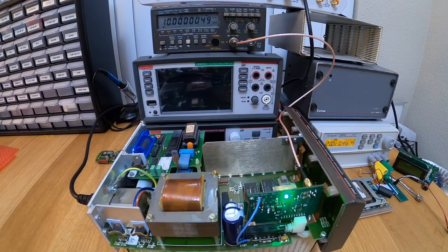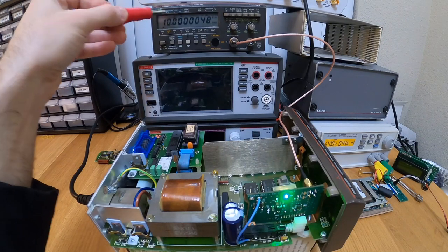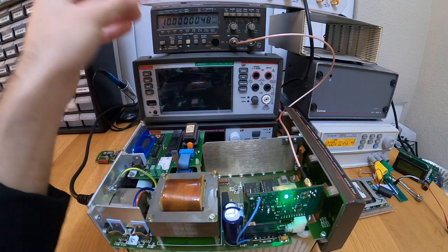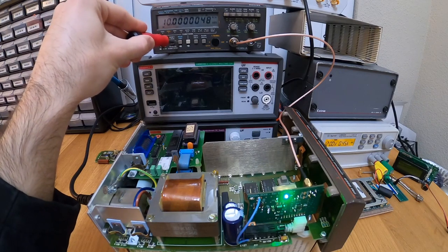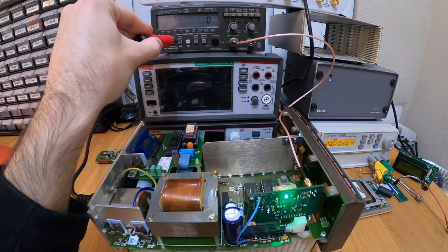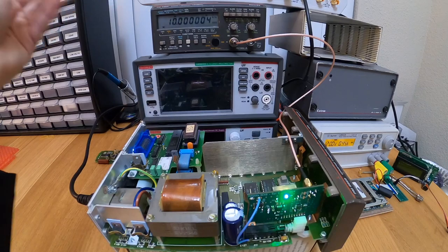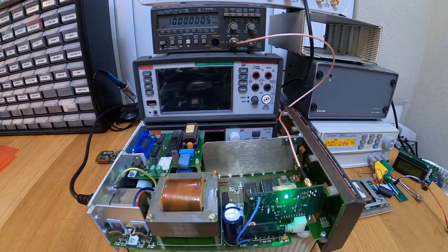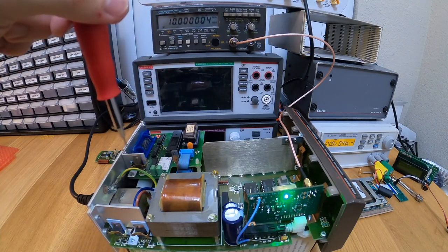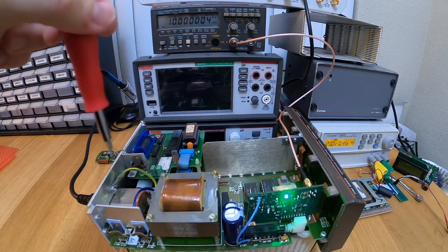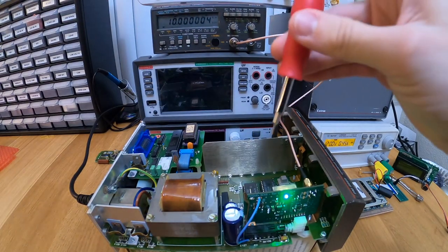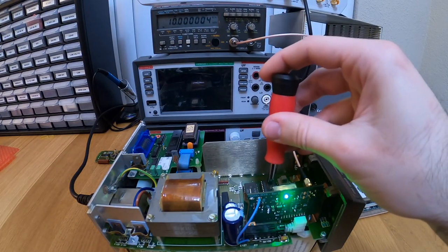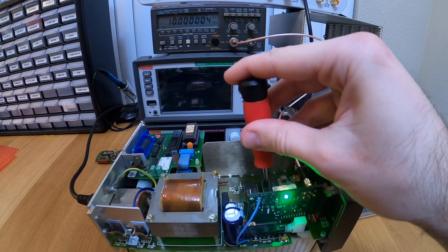So the first thing I want to do is do a coarse calibration. Currently, the reading frequency of the display here is 10 seconds, which is going to be a bit slow and inconvenient. So I'm simply going to change the measurement time to get a reading every second. I have less resolution, but for the initial calibration, it's going to be good. Just a word of caution: this instrument has AC live here, so just be careful. And this video is for professionals. I assume you have the knowledge to assess the risk properly.